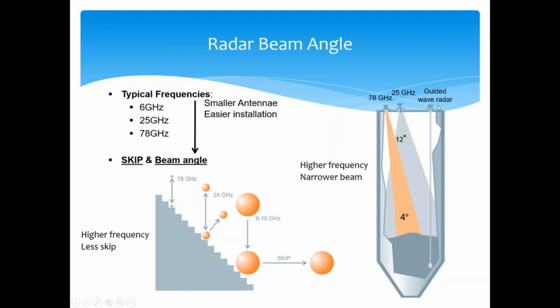In the past, you might have seen people use a guided wave radar for this. One of the biggest problems with putting guided wave in a solids application is there's a lot of force that acts upon this cable, and we've seen plenty of times where that cable gets snapped or broken off simply by those forces. So how do I kind of relate this?